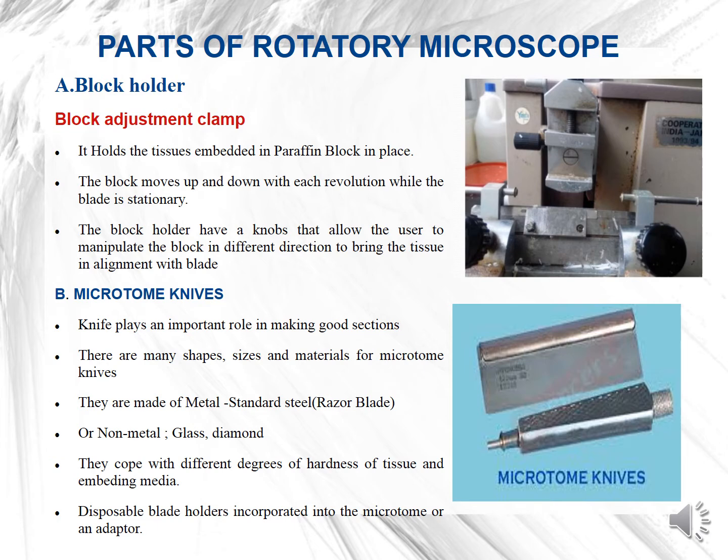The block holder has a knob. Here we can see the two knobs are present that allow the user to manipulate the block in different directions to bring the tissue in alignment with the blades.